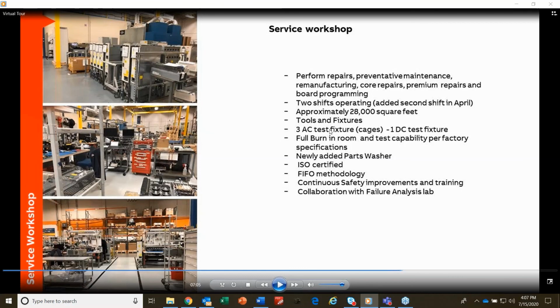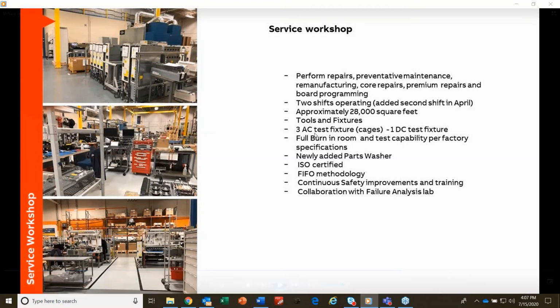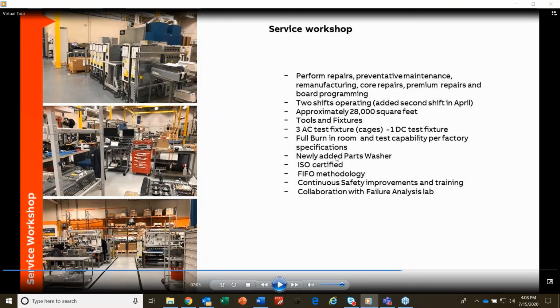This is a 28,000 square foot facility. We have lots of tools and fixtures to do the testing. When we do maintenance and repair, we run the unit through a full test, just like we do when we make the unit, to make sure it's going to withstand and that we've addressed the problems the customer sent it back to us for.